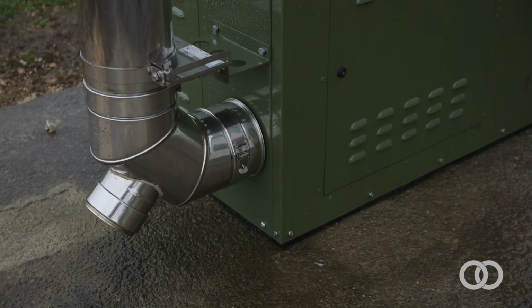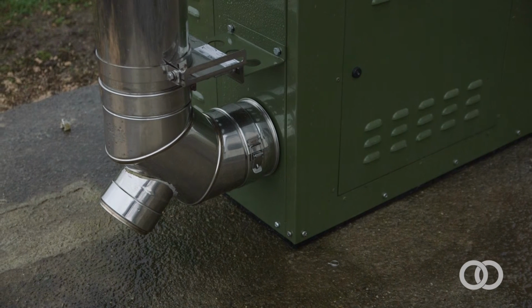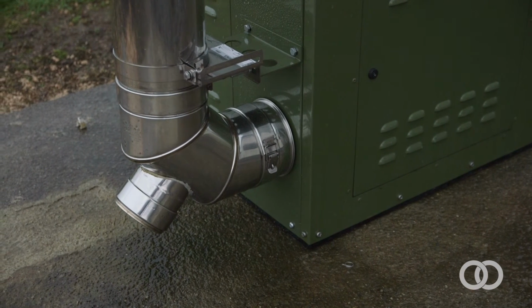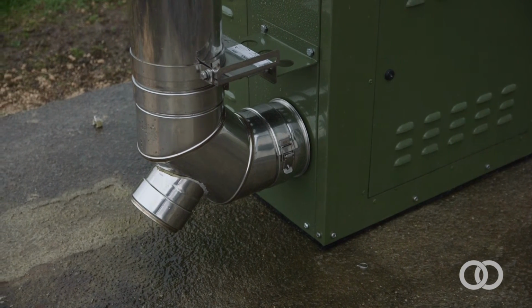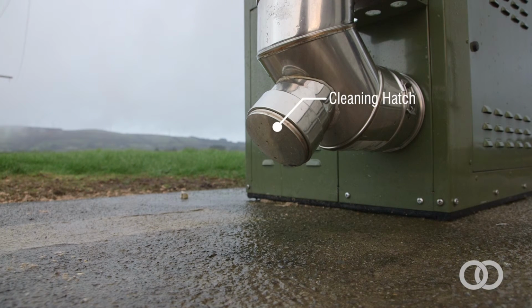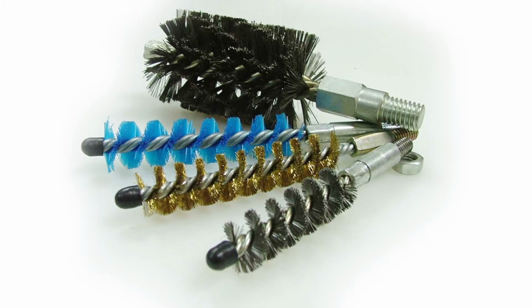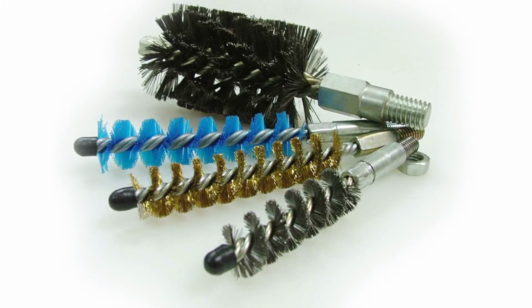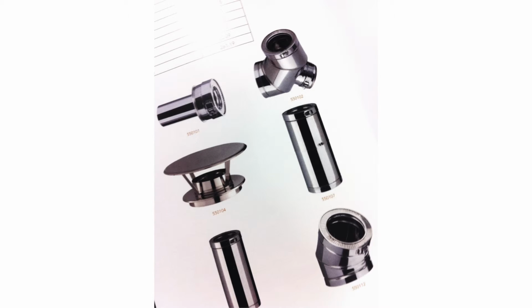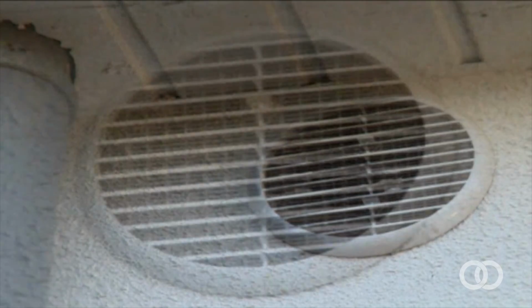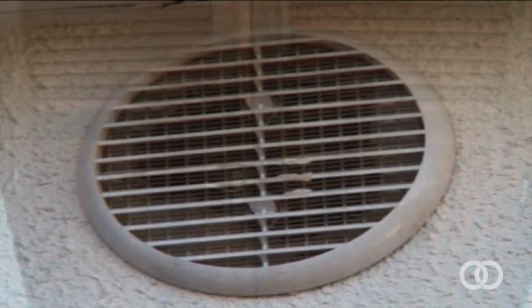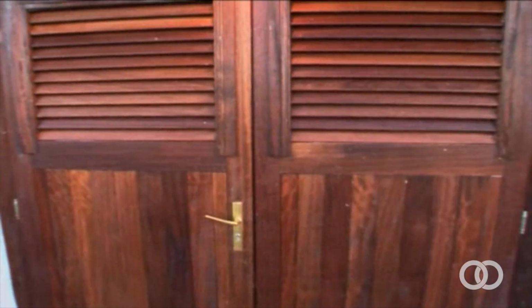It is important there are no other 90-degree bends used on the flue system apart from the 90-degree elbow at the rear of the 28 kilowatt boiler. A cleaning hatch or way of removing a piece of flue to enable annual cleaning of the flue needs to be provided at any 90-degree bend. A full range of straight, offset, elbow and T elements are available. For boilers located indoors, external ventilation by way of louvered doors or vent must be provided.